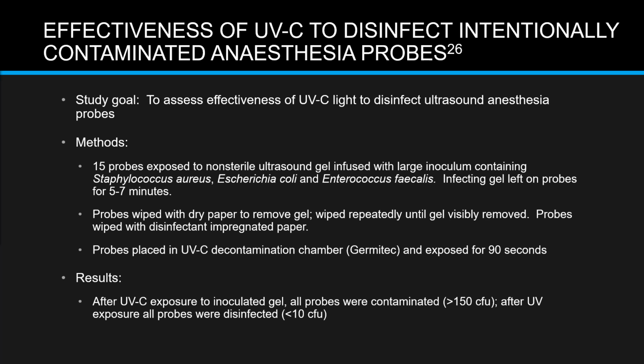The probes were wiped dry with a paper to remove the gel, and they were wiped repeatedly until the gel was visibly removed. And then they were wiped with a disinfectant impregnated paper. The probes were placed in a UVC decontamination chamber by Germitec and exposed for only 90 seconds. Before UV exposure, all probes were contaminated. After UV exposure, all the probes were disinfected. So there we have demonstration that the UVC was effective in disinfection. Next slide.